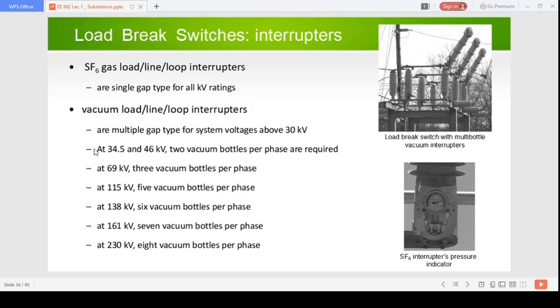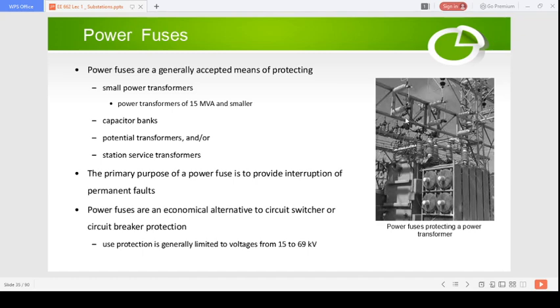At 34.5 and 46 kV, typically 2 vacuum bottles per phase are required, and at 69 kV 3 of them are required. At 115 kV, 5 of them are required, and you can see that as the voltage rises, the number of bottles needed to quench the arc or perform the interruption increases. For 230 kV you need 8 such bottles. So as the voltage increases, the length of this device increases, so the size of the load break switch will also increase.